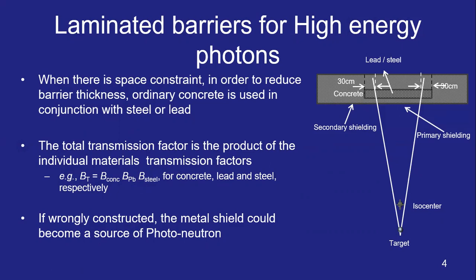One thing to be very careful about is that whenever you have a metal in the barrier, the metal could become a source of neutrons. So the concrete behind the metal should be able to absorb those neutrons. Therefore, if wrongly constructed, the metal shield could become a source of photoneutrons. One has to be careful about that.